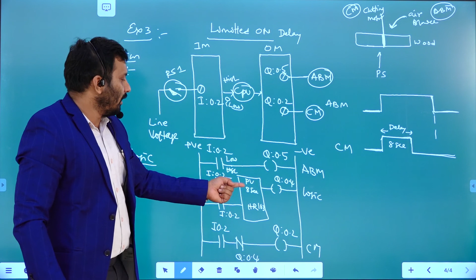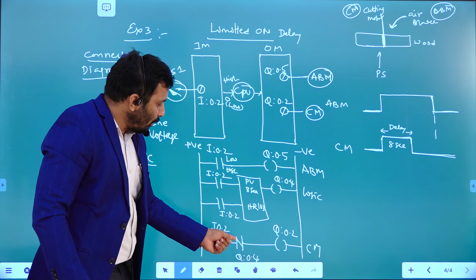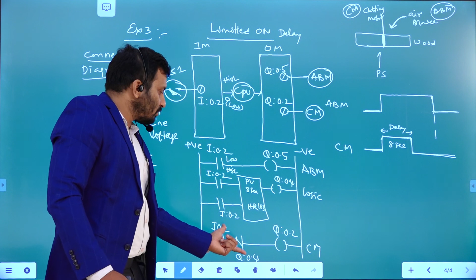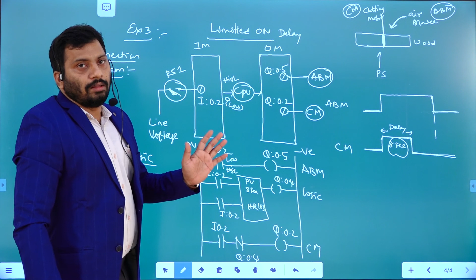Whenever this value keeps incrementing with the clock, and it becomes equal to this time delay, after 8 seconds, what will happen? This is going to be high. Why? Because the holding register value and the preset value are going to be equal, right. Then this output is going to be high. Up to that time, this is low only. Whenever this output is high, it is the same as giving the address to this particular normally closed contact, right. So whenever this is high, the normally closed contact is energized and it is going to open. When it's open, this output is going to be low. That is the reason after 8 seconds this cutting machine is going to be off, right.